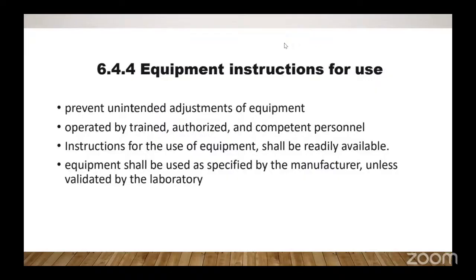I remember one time we were using one of the equipment, I don't want to mention which, every 7 days the creatinine onboard stability expired and you had to throw it away. Sometimes we don't even use up that number of test kits in that period. So we did a validation, and we saw that it could still be sustained for 14 days. It was well documented and passed.